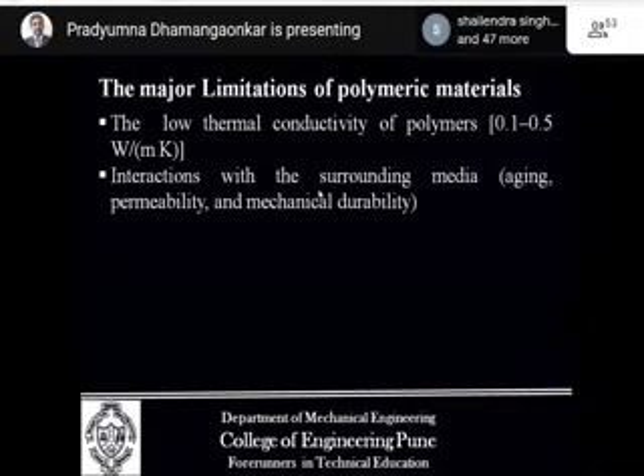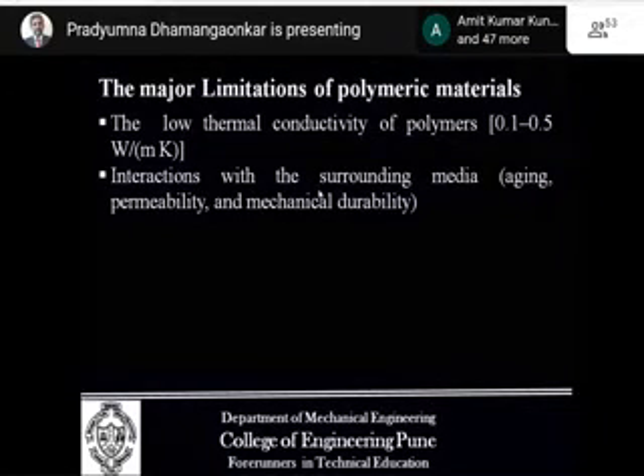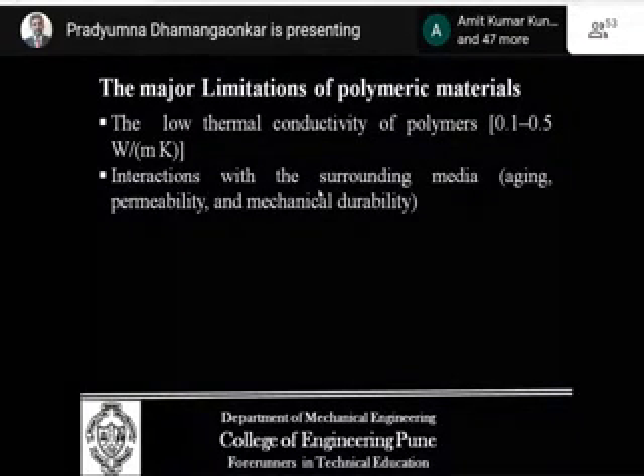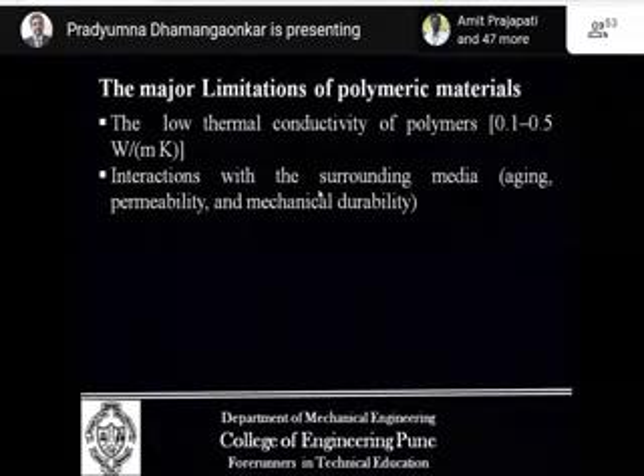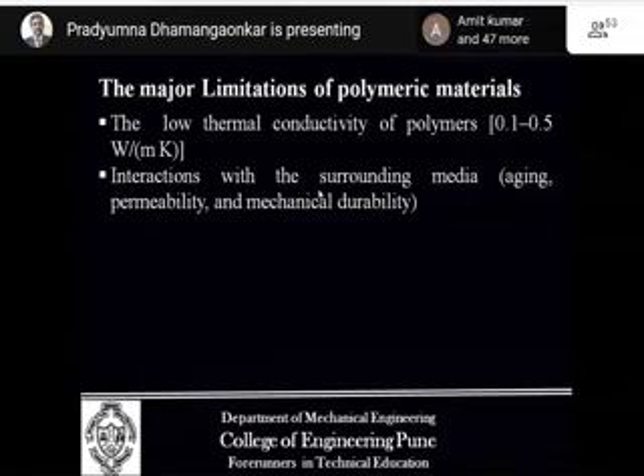Interactions with the surrounding media, that is aging. As we know, if we keep a polymer or a plastic material outside our house, after some period of time, some months, we find that the plastic or polymer gets decayed. It loses its strength, it loses its quality, and hence this is one of the major problems with polymer heat exchangers, that it has an aging effect, and thus there is a problem with the mechanical durability.